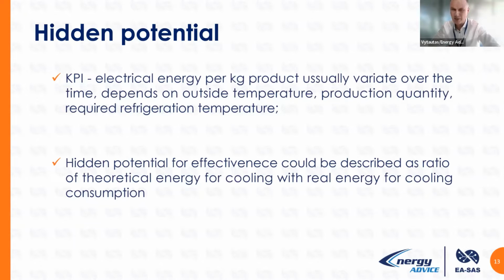And as we describe hidden potential, especially when we are looking to reach CO2 neutrality, we should always know what the hidden potential is. What does it mean, hidden potential? We need to calculate a ratio: the energy required theoretically for cooling, chilling, or freezing, divided by the real electricity consumption for that process. One means you consume the theoretical energy, and better is impossible. A lower ratio shows your potential, how far you are from where you could be with the technology. And of course, a digital twin online can describe where you are.